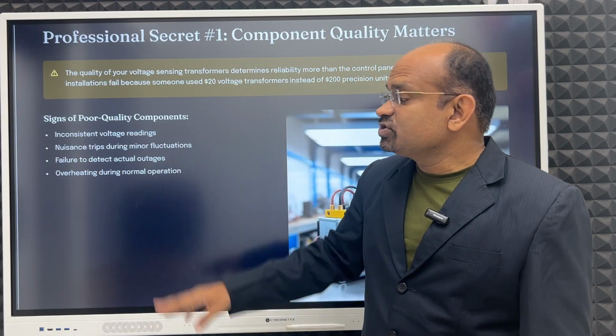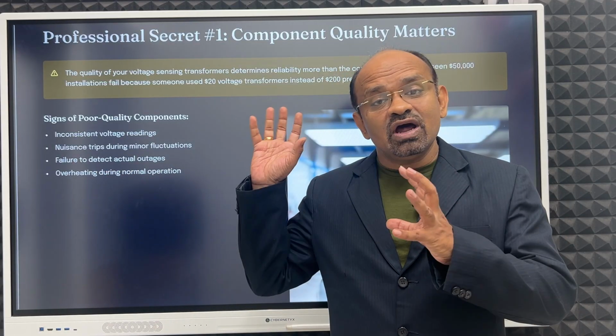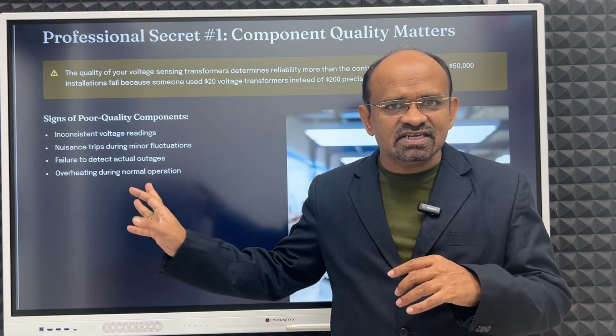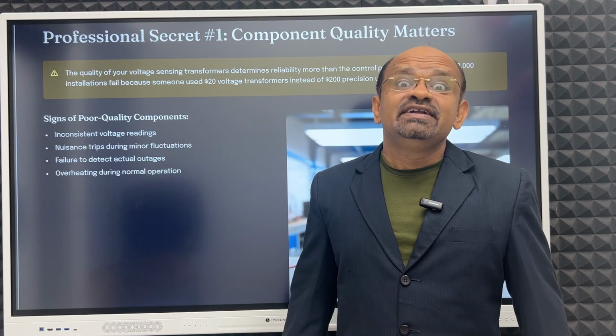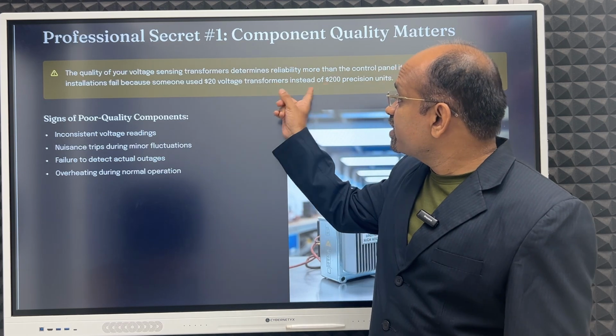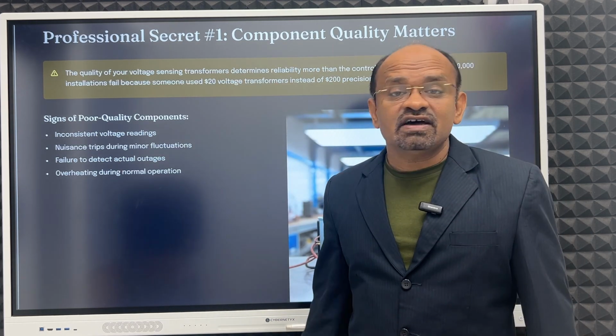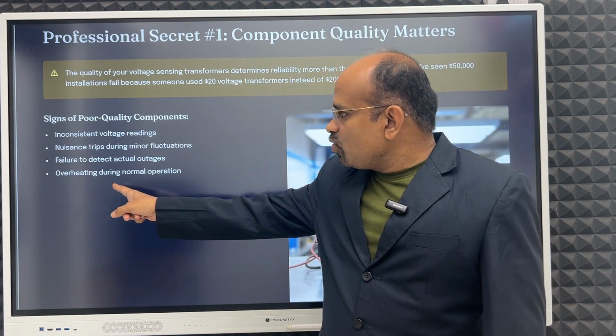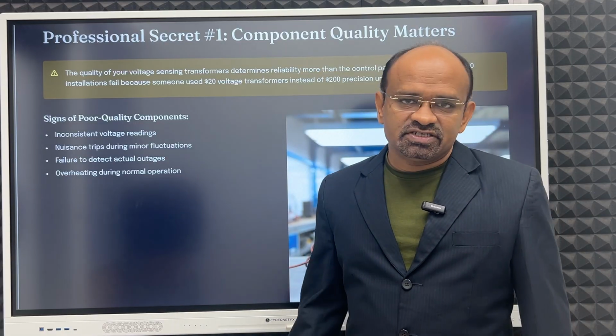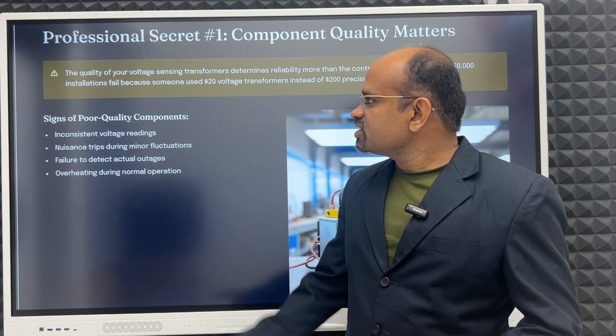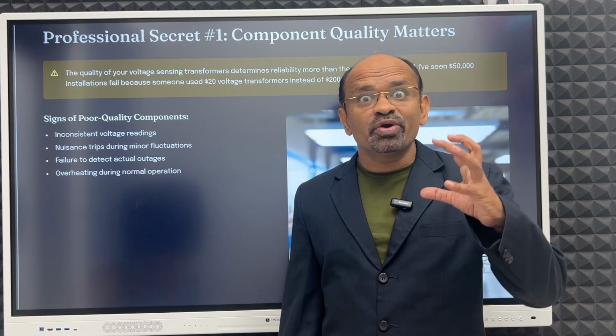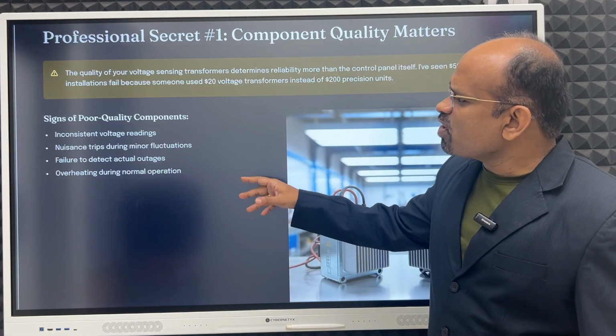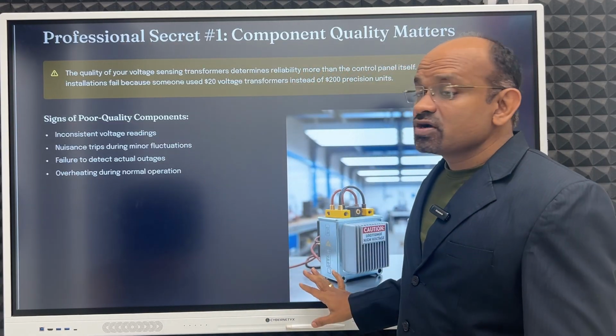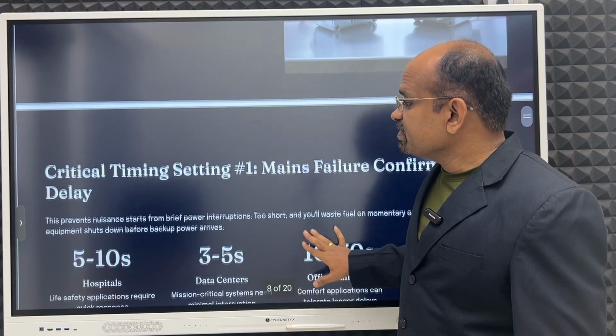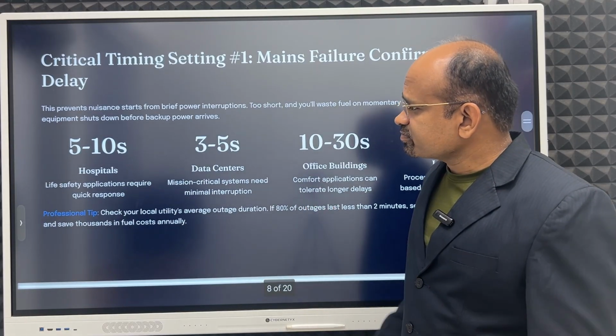Failure to detect actual outages. Actual outages happened, power is gone, but still it is not able to detect it. So that is the problem because of this inferior transformer. Then overheating during normal operation. During normal operation, this cheap transformer will overheat. Okay. So these are the problems if you don't use a good quality potential transformer or voltage transformer.